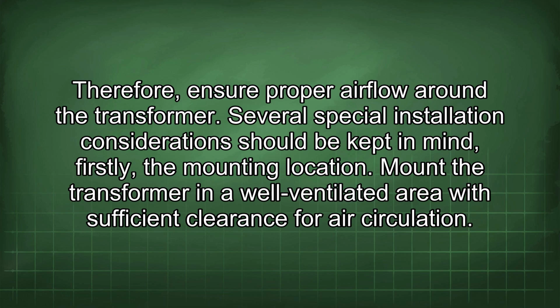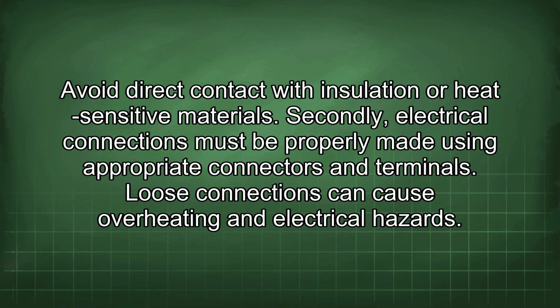Several special installation considerations should be kept in mind. Firstly, the mounting location. Mount the transformer in a well-ventilated area with sufficient clearance for air circulation. Avoid direct contact with insulation or heat-sensitive materials. Secondly, electrical connections must be properly made using appropriate connectors and terminals. Loose connections can cause overheating and electrical hazards.